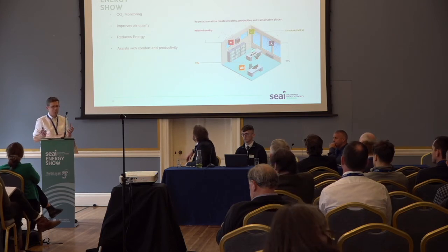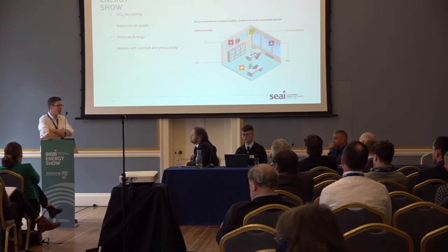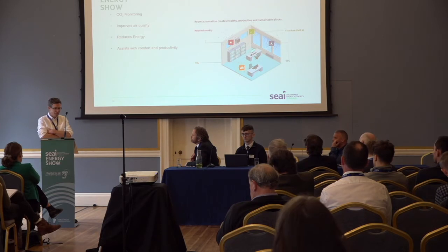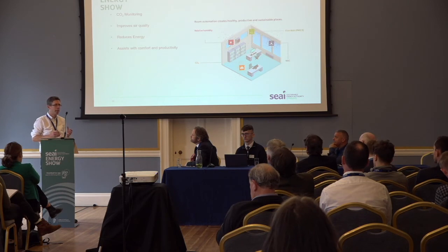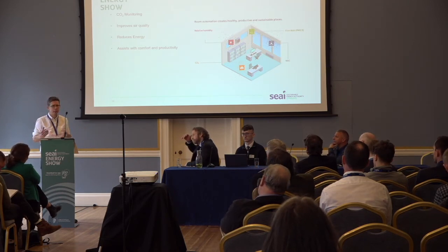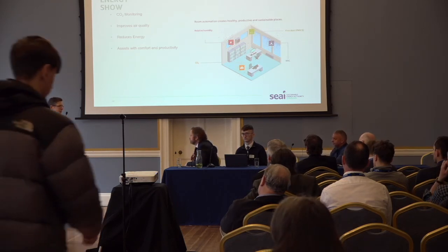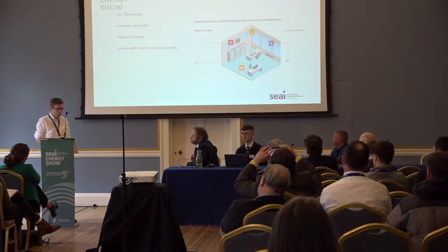Fan power makes a massive difference to our energy use, so if we drop the ventilation a bit, we get good returns on fan power. It shouldn't take a lot of work - yes, we have some dampers to put in, but in the majority of cases we already have the CO2 sensors in relatively new buildings. And there are always wireless solutions for CO2 sensors you can retrofit.